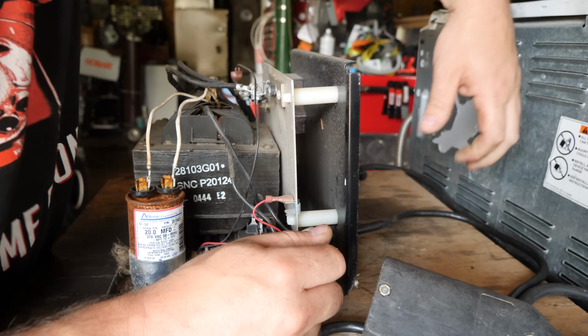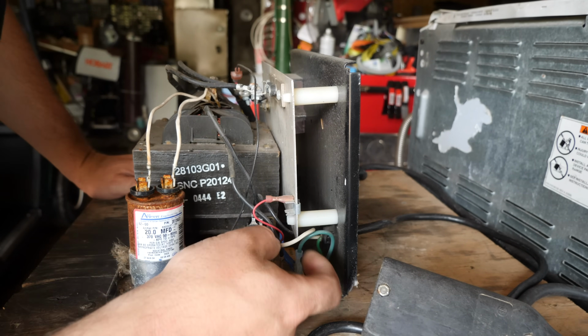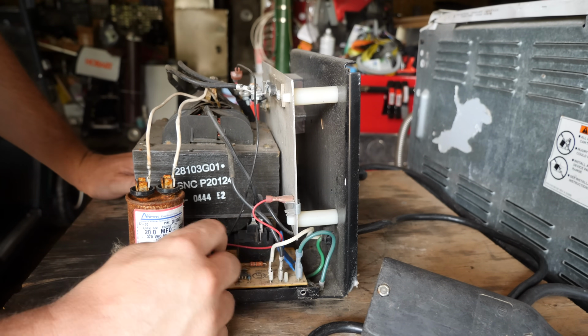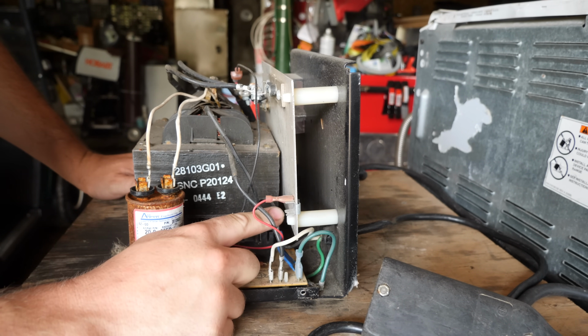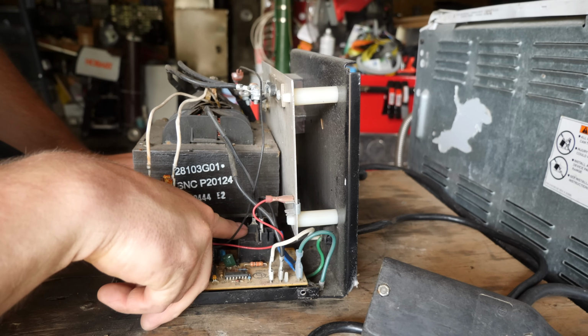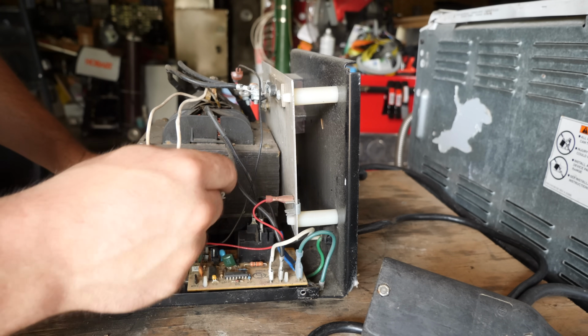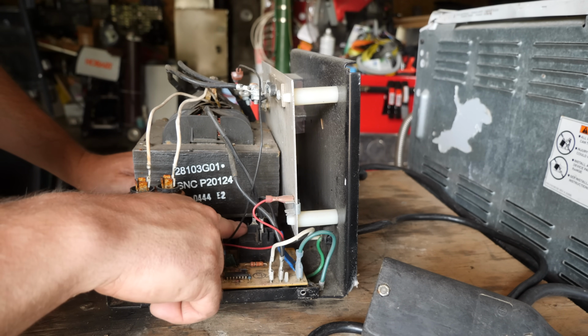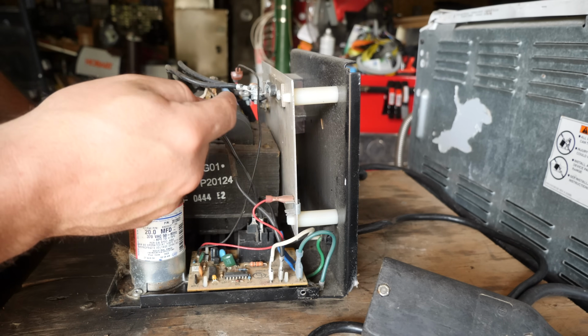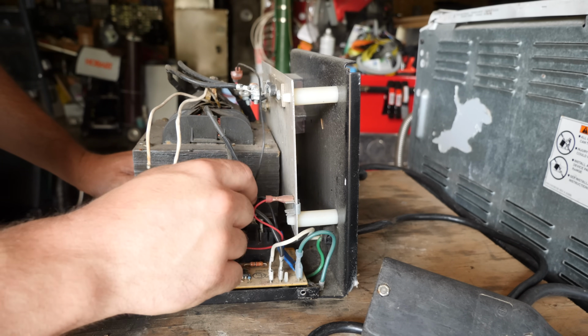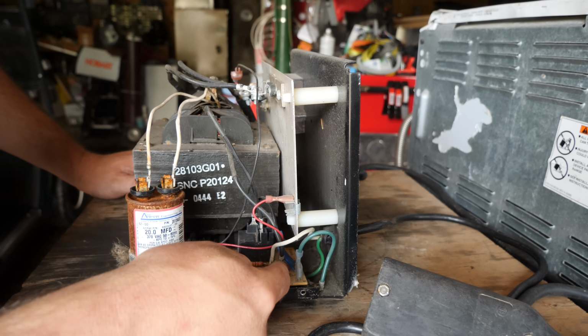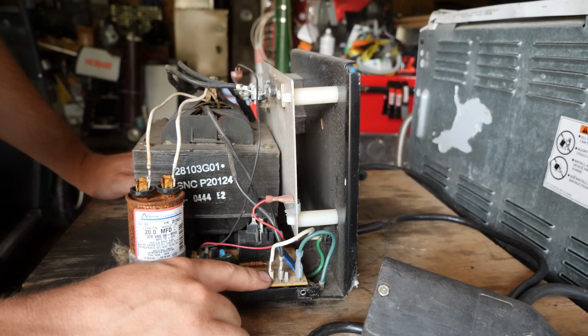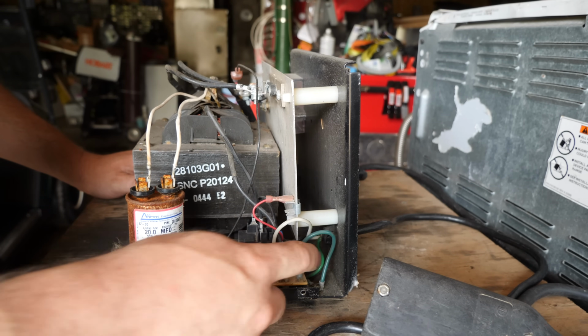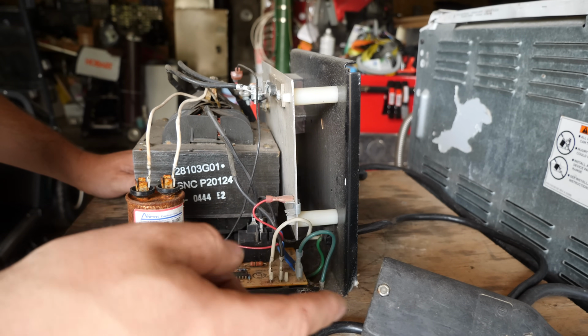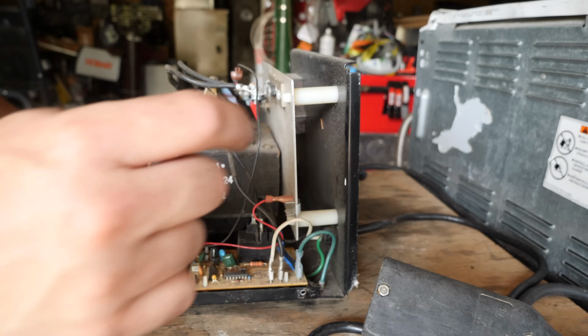This is our 120 volt line set right here. Our hot lead goes first into the relay, and then out of the relay into the transformer. The other winding goes onto this board here, which is commoned to the neutral. Our ground is chassis grounded, which is plug grounded, which is then grounded on this board as well.